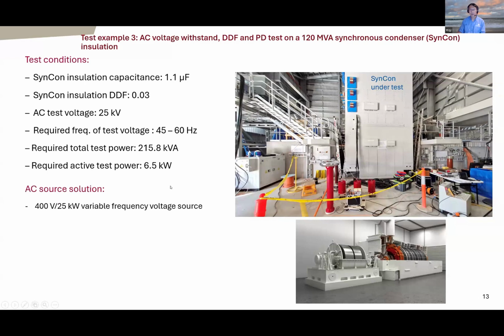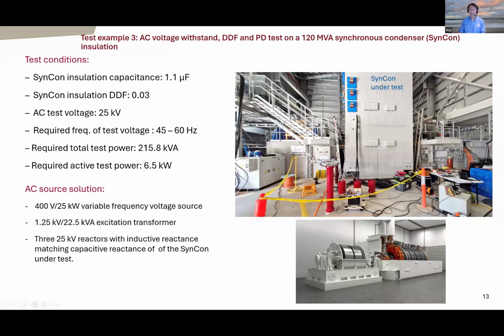So what you can do is use a variable frequency source, 25 kilowatt, and an excitation transformer somewhere here. Then you use a set of reactors with the reactance matching the capacitive reactance of the test object. By varying the frequency, you more or less line these two reactances up close to 50 hertz, but you can never match them well enough. So by varying the frequency, you can tune the Q to get your required voltage, and only this small equipment can supply this gigantic machine. The matching in this particular case was done so well that in the end we didn't need to use variable frequency. We just used a normal 50 hertz mains variac. So this is a very good example of how the voltage is generated for testing these big test objects.